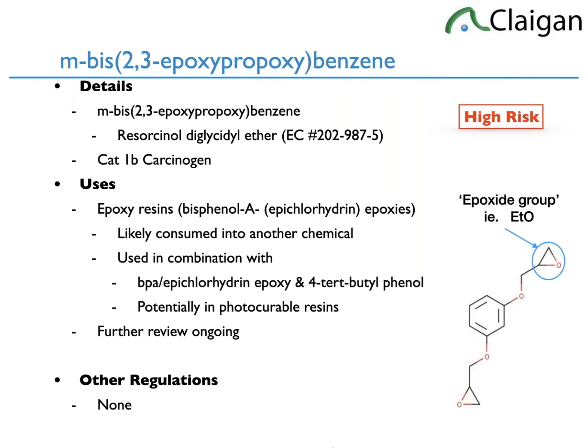So this is SVHC, be less of a problem because any epoxy is a chemical until added to the article, and then any residual amount of this would be measured over the weight of the adhesive and the article it's adhered onto, the component. Not true for MDR, it's material in contact. So it's whether or not it's above this concentration in the epoxy, which is possible because it could be 20 to 30% of the original epoxy hardened. That's an epoxide group.